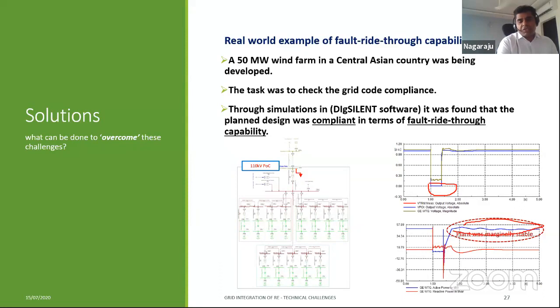So the plant was marginally stable, but it was failing one of the criteria, which is that the power should not have oscillations beyond a few cycles. In this case, because they had already purchased the turbines and the design was nearly at the execution stage, they sought an exemption from the grid operator for this particular aspect.